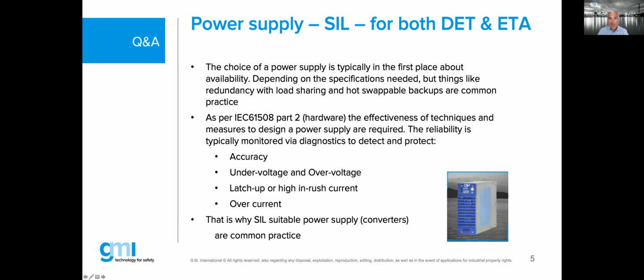It's all about the accuracy, the under voltage versus the over voltage, the latch up or high inrush currents when you actually start up the power supply or you replace a hot swappable power supply, and the overcurrent. Now, the choice of the power supply depends on the specification needed. But things like redundancy with load sharing and hot swappable backups are very common practice. And I can say yes, rating your reliability on the choice of the power supply is a very correct item to investigate. Unfortunately, in the industry today, among the commercial SIL verification calculation tools, not many are actually taking into account the reliability of the power supply to your final elements. It's often forgotten. But that's something that needs to be considered, and should also be considered in the future by those commercial packages available in the market.